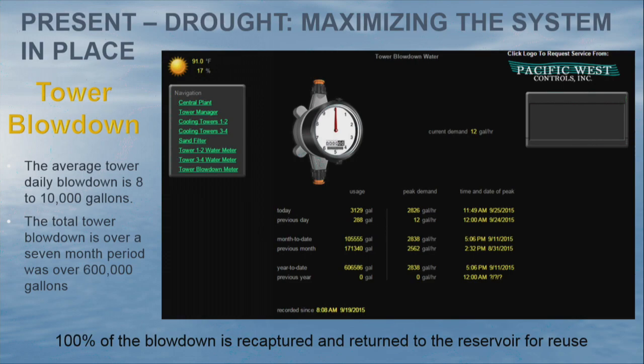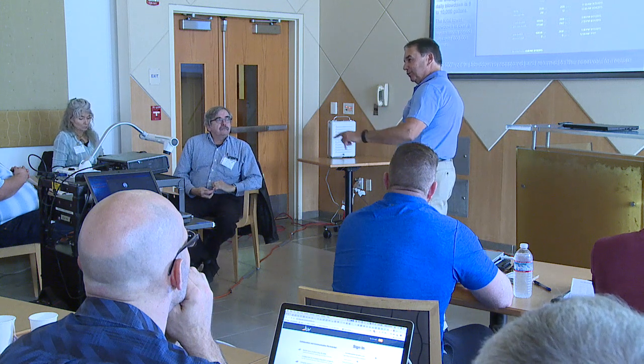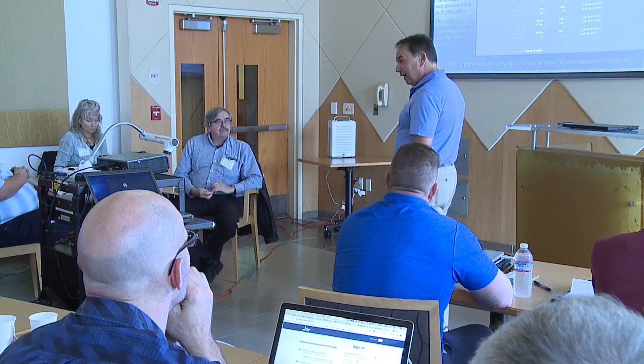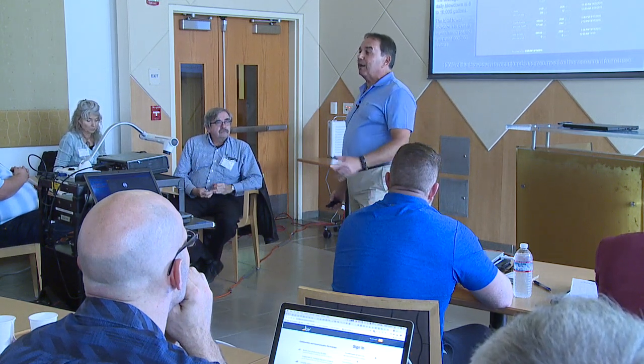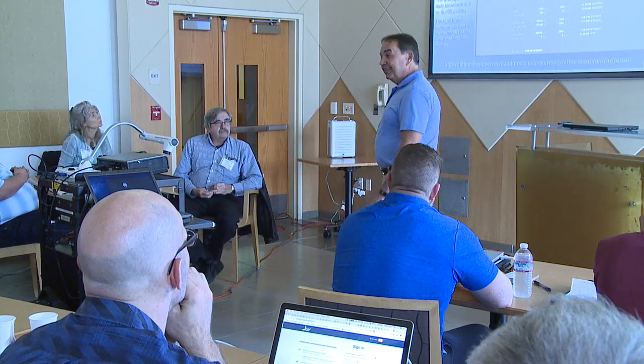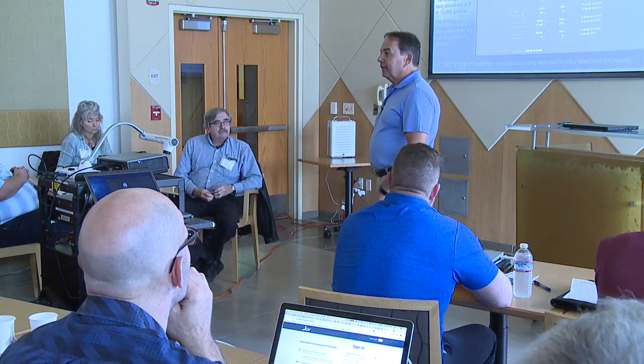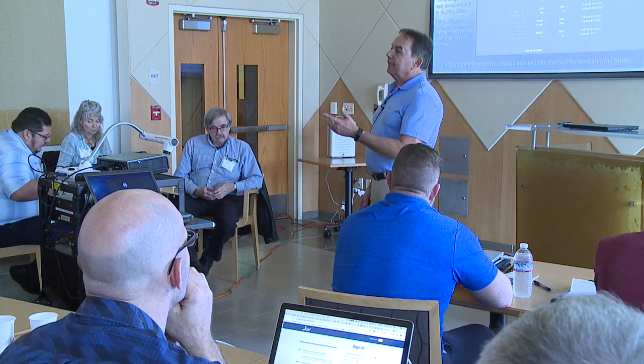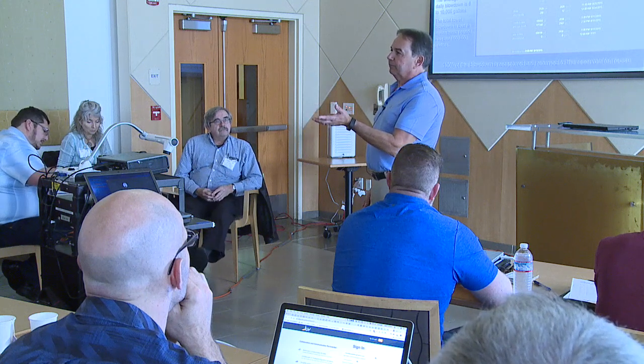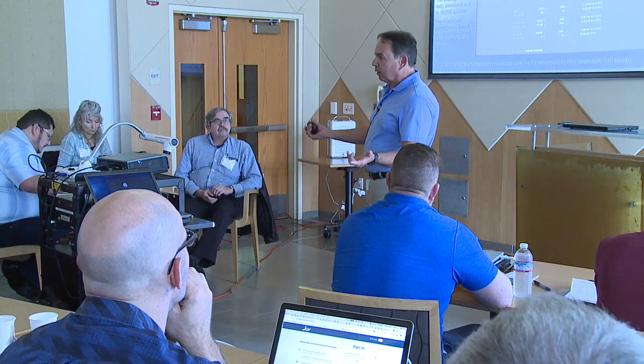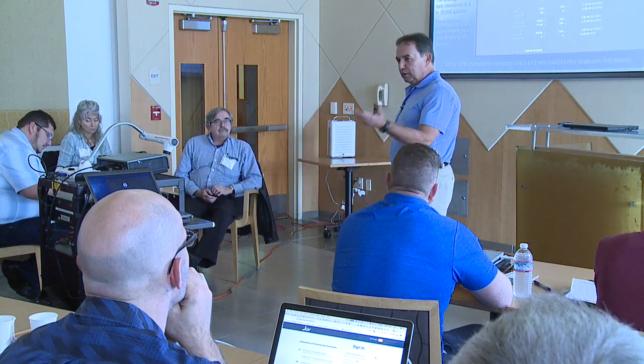We repiped the blowdown instead of going to the sewer. We repiped it back to the lake. We put a meter on it so we collect and see exact numbers of how much is blowing down. That could be 10,000 gallons a day, every day you operate, that would have gone to the sewer system. And not even thinking about the costs, because we pay the city of Turlock to take our wastewater, we reduce costs there as well.